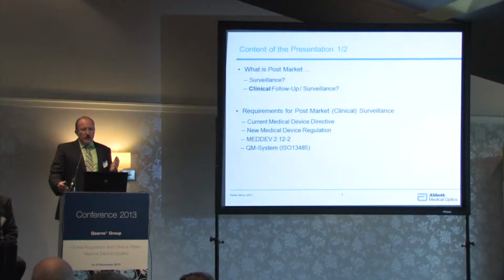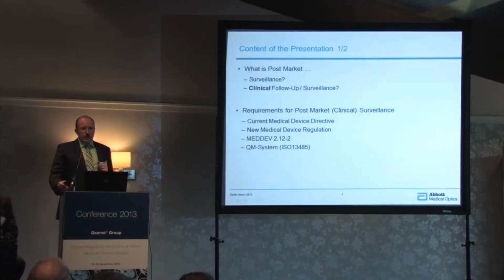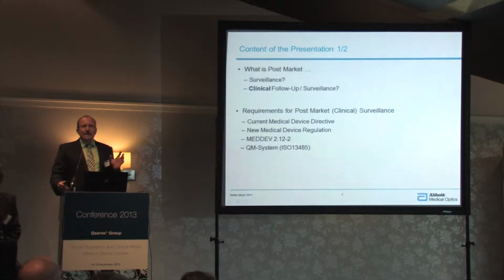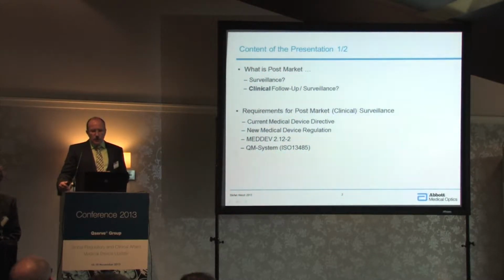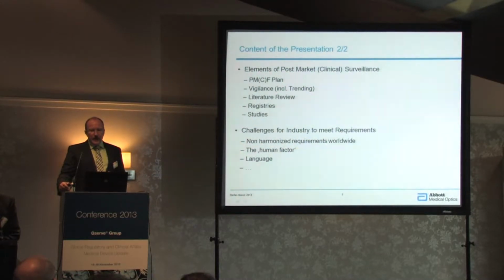I want to talk about the requirements for post-market clinical surveillance, touch a little bit on the current Medical Device Directive, and also give you a slight outlook as much as I can. Everything is still in flux related to what's coming up, or what might come up in the future. And then also refer to the MEDDEV that Dr. Higgins already mentioned to us, and touch a bit on what is in ISO 13485 that speaks to post-market clinical surveillance.